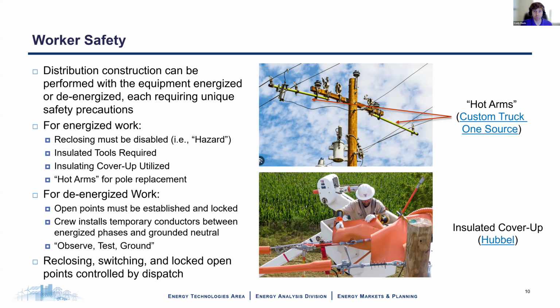A philosophy that you hear a lot with energized or de-energized work is observe, test, ground. What that means is when the crew gets out there, before they do any work, they're supposed to look and make sure that things look like they're dead, that any grounds that are supposed to be in place are already in place, or any open points that are supposed to be open are actually open. They'll do a test to make sure that the conductors aren't still energized, and then they'll place their grounds. And that helps to protect them and adds an extra layer. And then again, reclosing, switching, and these locked open points are all controlled by dispatch. That is one of their functions, to track, maintain, and ensure worker safety by controlling those points of worker protection.